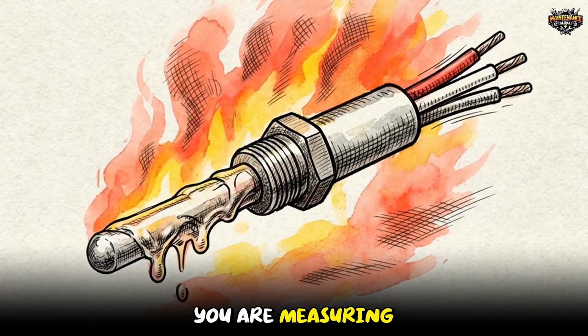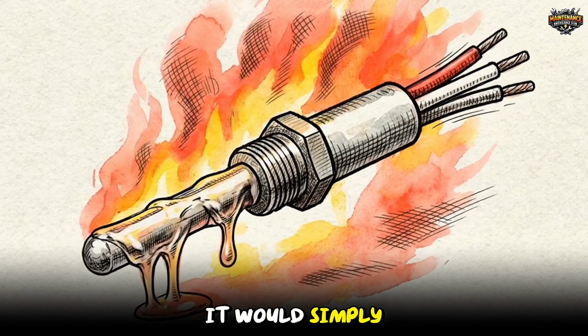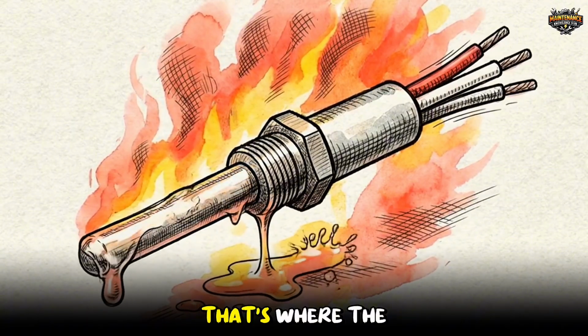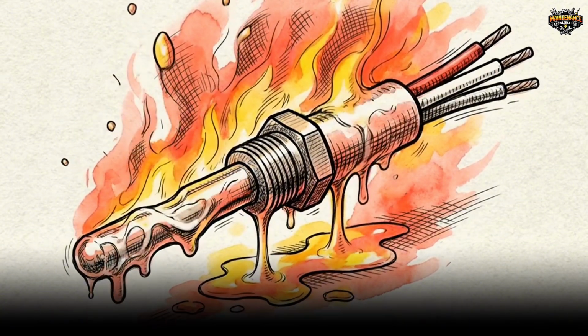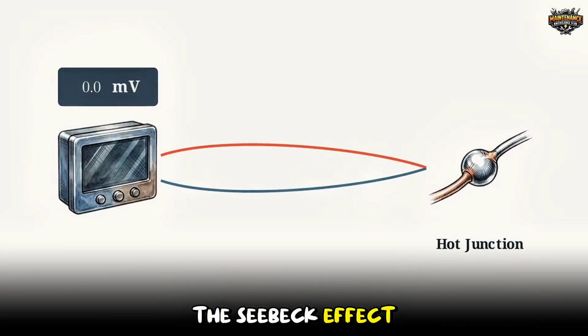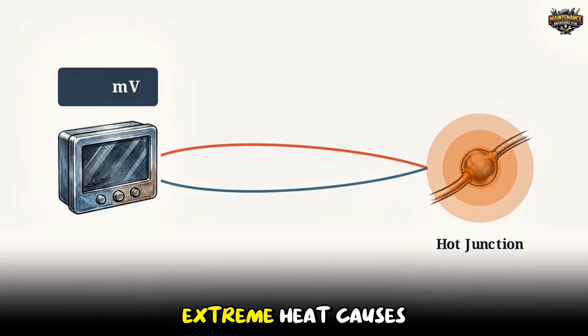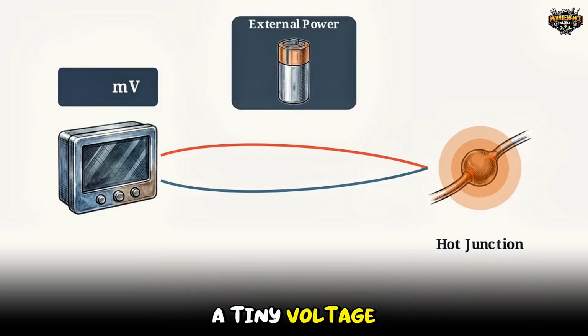But what if you are measuring an environment so hot it would simply melt a platinum RTD? That's where the thermocouple comes in. Thermocouples operate on the Seebeck effect. When two different metals are joined at a hot junction, extreme heat causes them to generate a tiny voltage. Astonishingly, this circuit needs no external power source. The extreme heat itself creates the electrical signal.